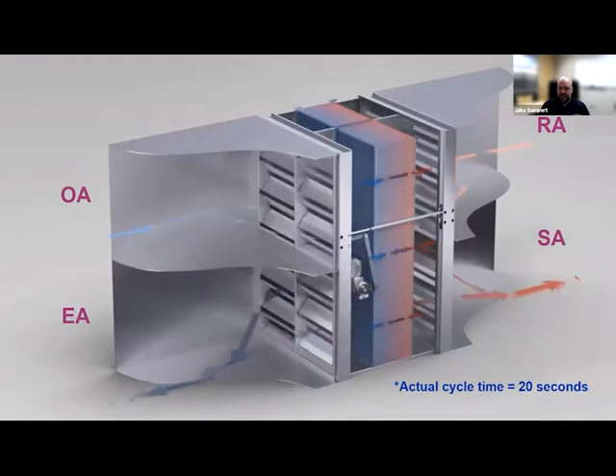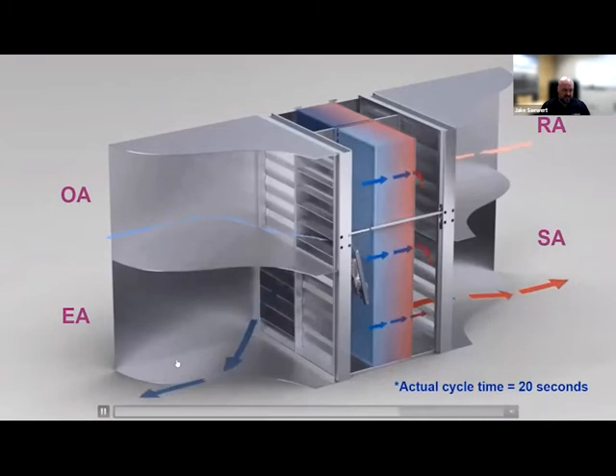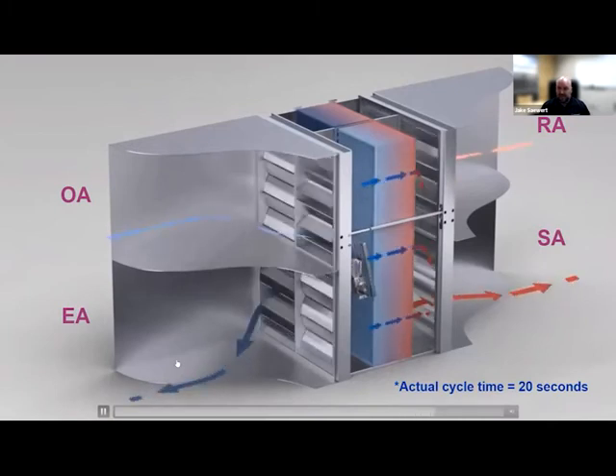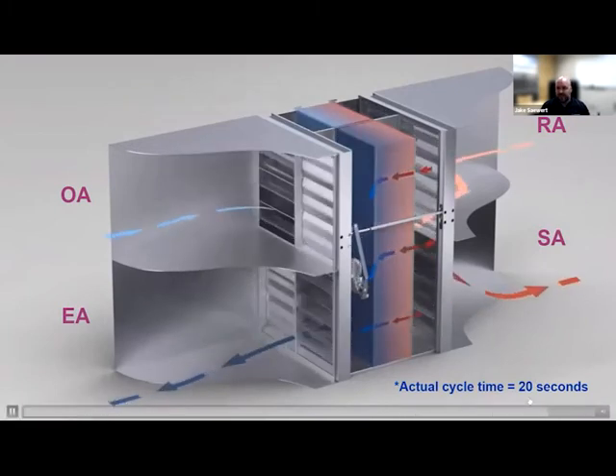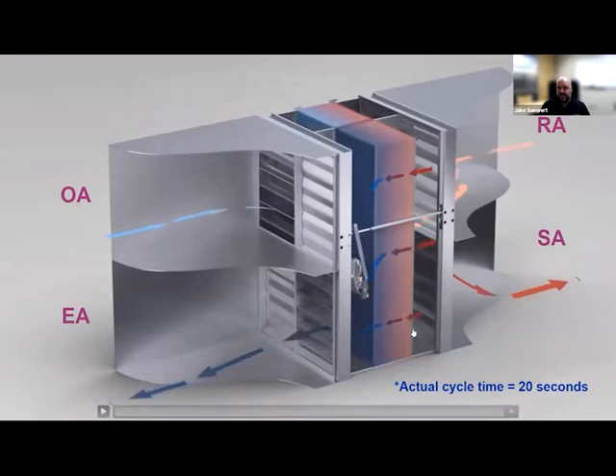So every 20 seconds, this is going to cycle, and that is a point that can be controlled as well. You could actually slow it down and modulate the capacity, especially for an economizer type condition.